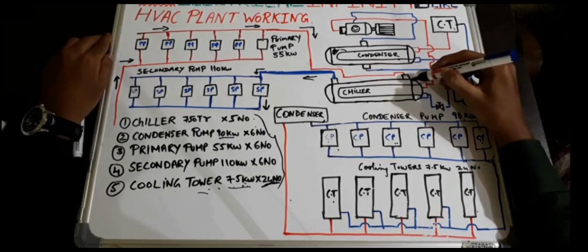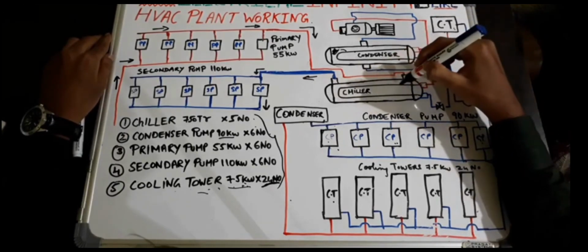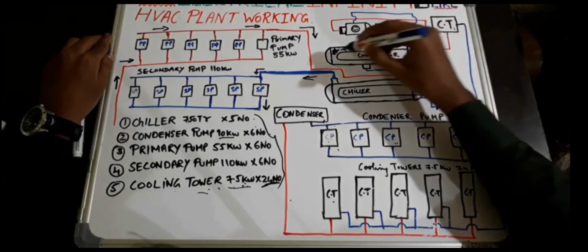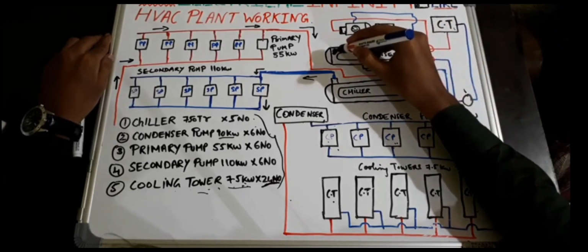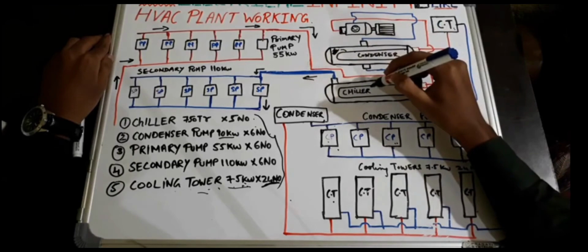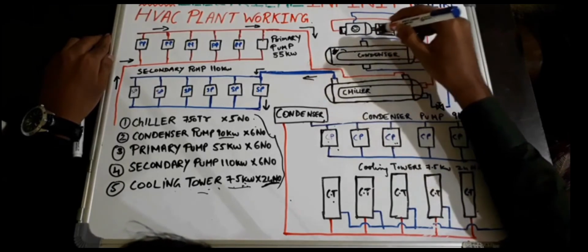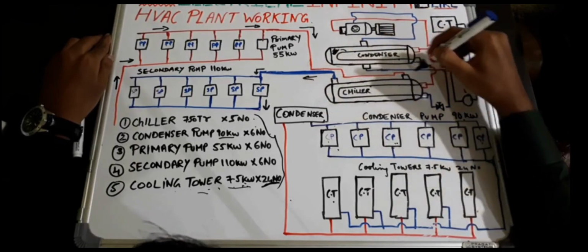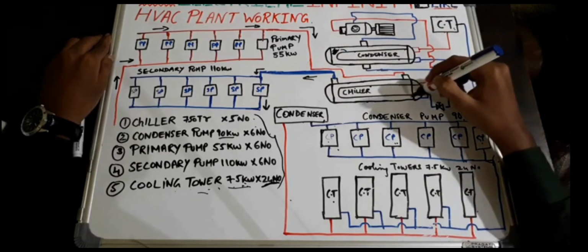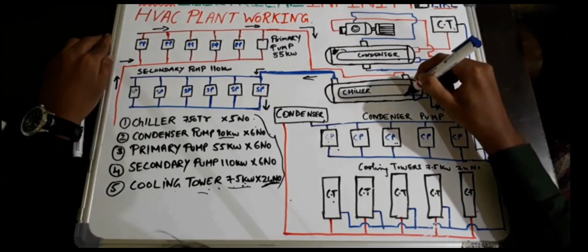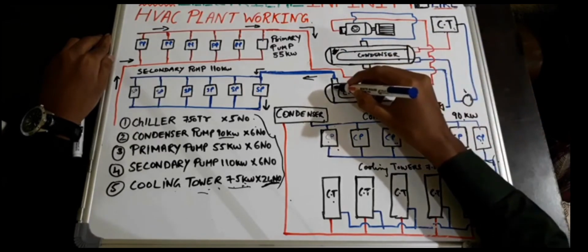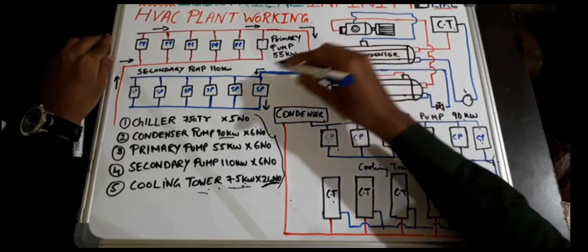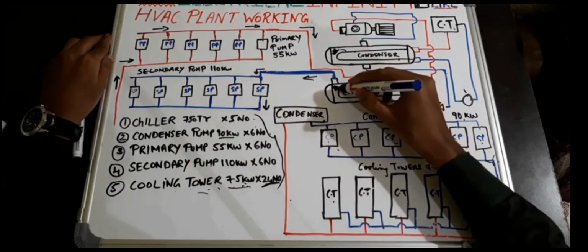Coming to the chiller, as you can see here, the refrigerant is present in the tube type. This refrigerant, which was present in the shell type in the condenser, is now present in the tube type. As you can see here, the refrigerant is transferred from here with the help of an expansion valve to the tube type of the chiller. And the water is present in the shell type of the chiller.